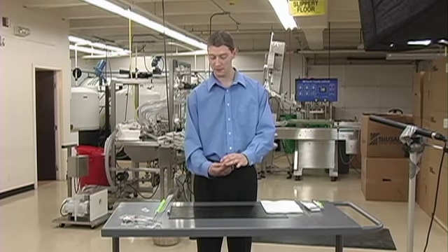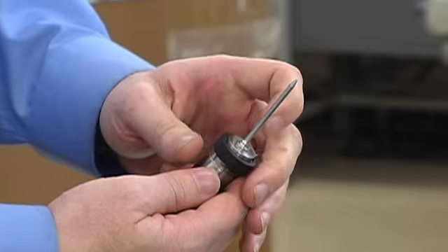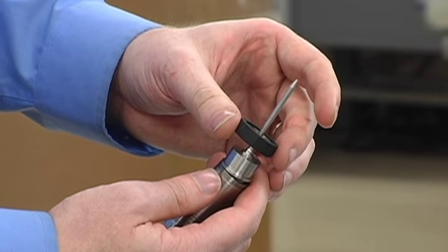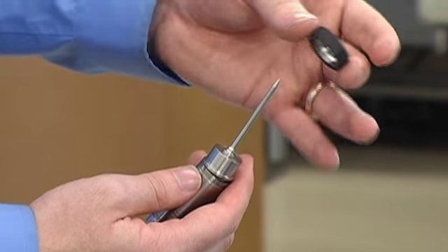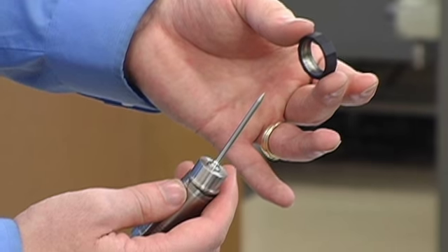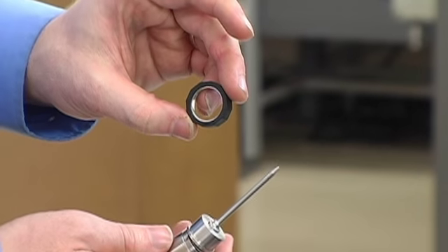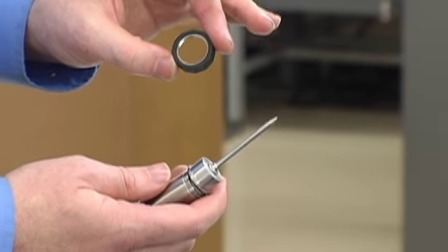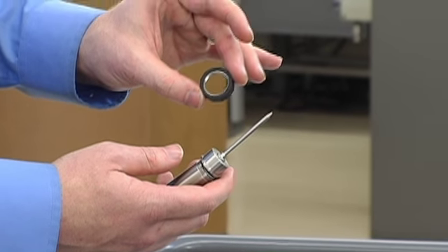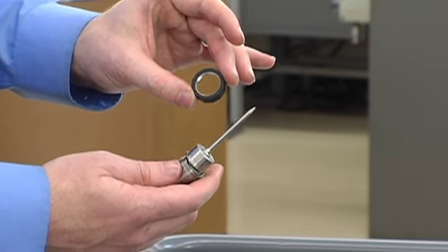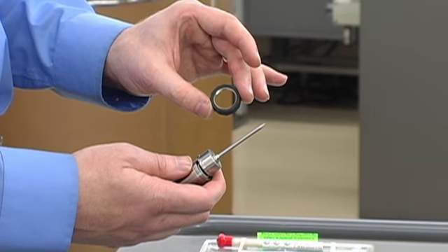Once you have the lock ring loose, then you're going to want to go ahead and lift the lock ring away with one hand, slide it over the temperature probe carefully, and then set this lock ring to the side. This lock ring could become damaged easily. It's very sensitive to shock, dropping on a hard surface.